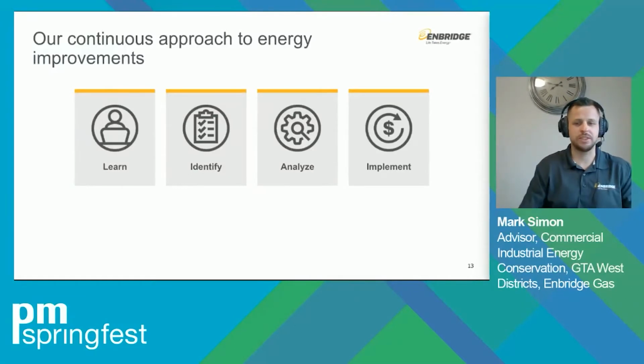What our programs are designed to do is meet with the customer, determine what their needs are, learn what they're looking for and what their overall goals are, to identify savings that could be there. It could be as easy as ensuring that their air curtains are working when their doors are open. A lot of our projects come from initiating that conversation: hey, maybe your drive-through dock doors shouldn't be open for 2 hours, 3 hours a day. We do implement projects to put on automatic timers and high-speed door closers, and they do tend to save quite a lot of money.